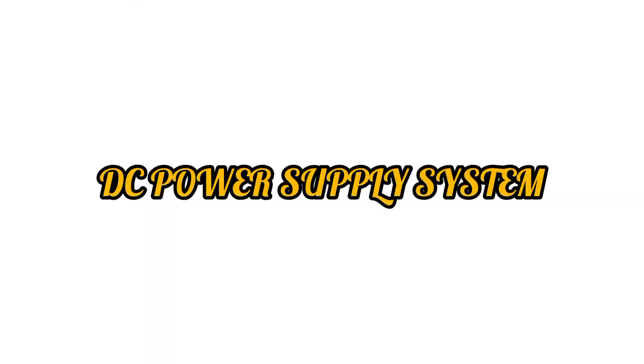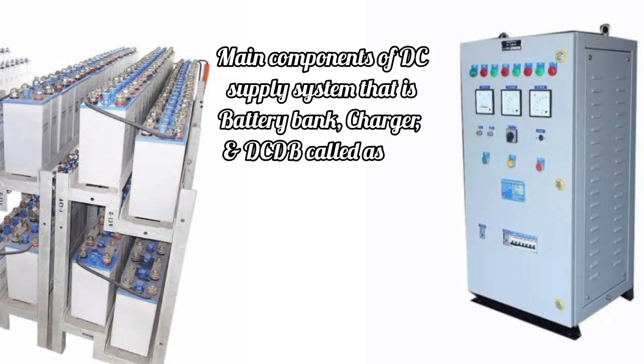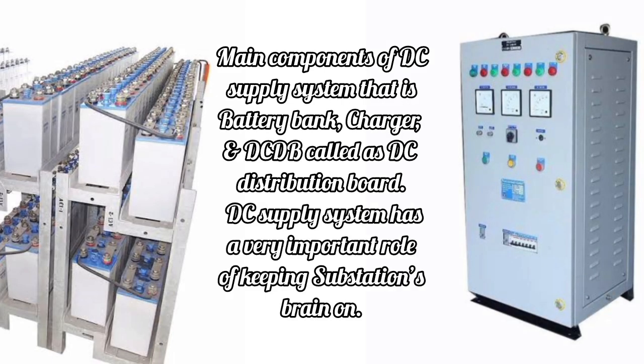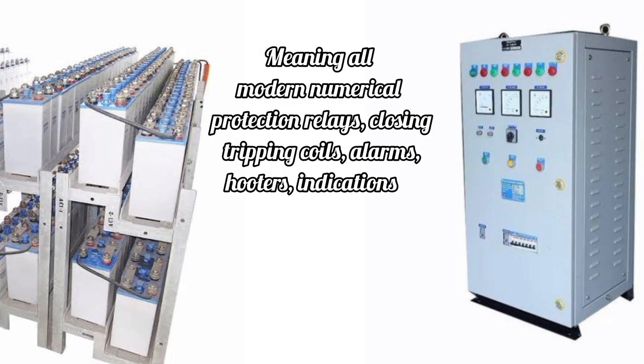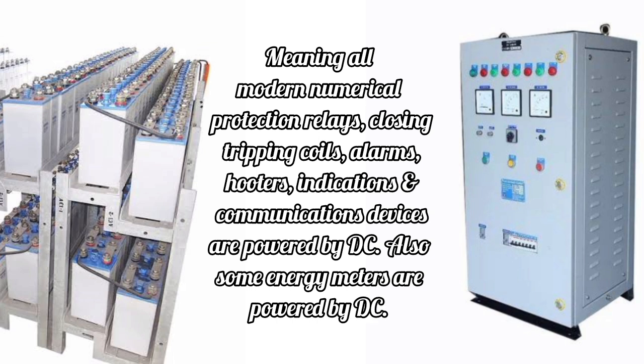DC power supply system. Main components of the DC supply system are the battery bank, charger and DCDB, called DC distribution board. The DC supply system has a very important role of keeping the substation's brain on. Meaning all modern numerical protection relays, closing and tripping coils, alarms, hooters, indications, and communication devices are powered by DC. Also some energy meters are powered by DC.